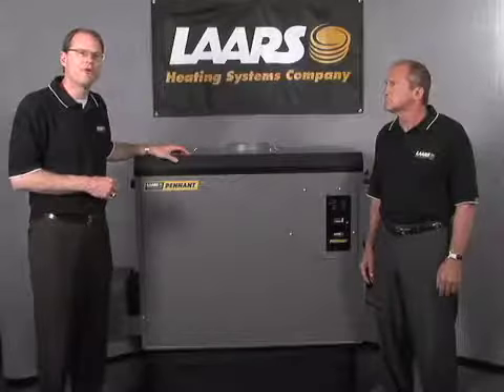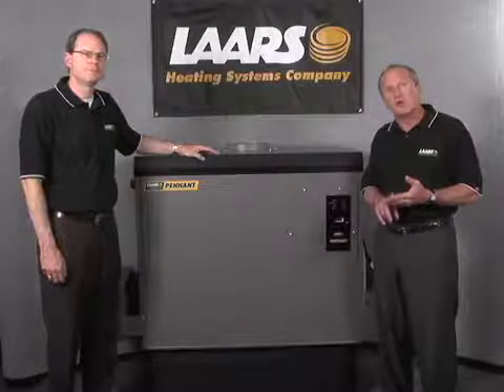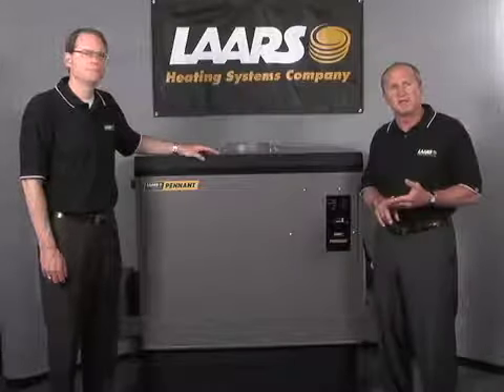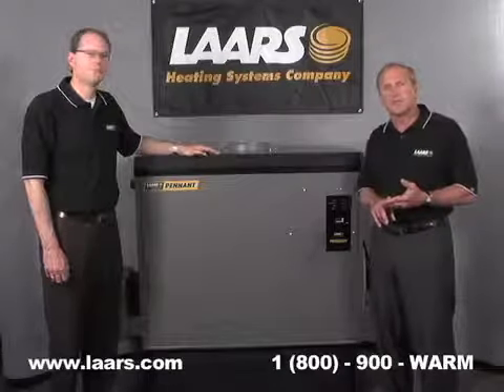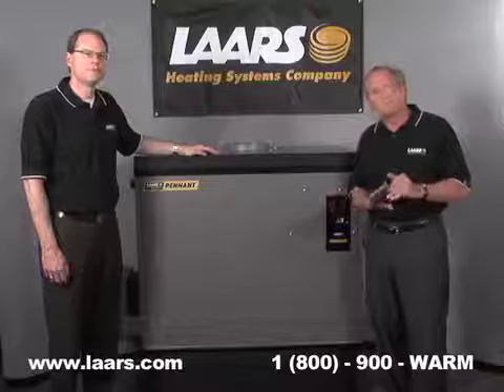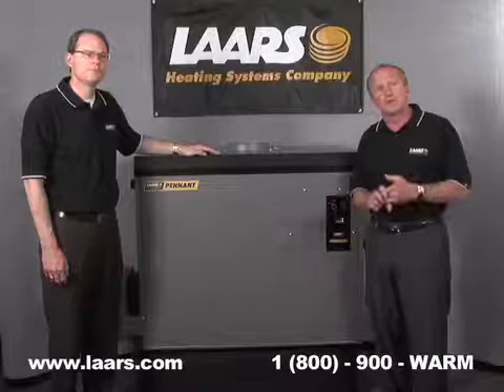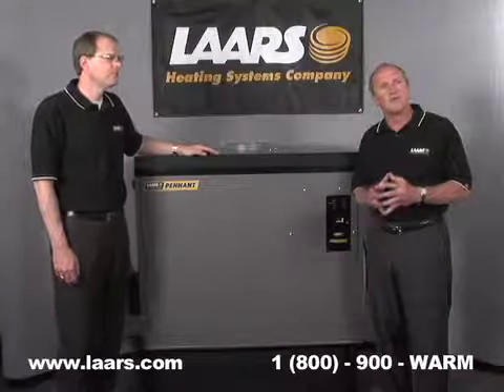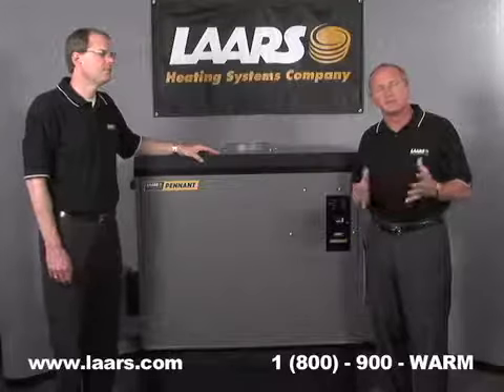So just to recap, this is an 85% non-condensing, low NOx boiler, meets all the nitrogen oxide emission standards that are out there. And we also live up to the AB 1953 standard, which is a low lead standard that has been initiated by California as well as Vermont. So we meet all those standards. It's a great product, horizontal in design, been out there for quite a while.